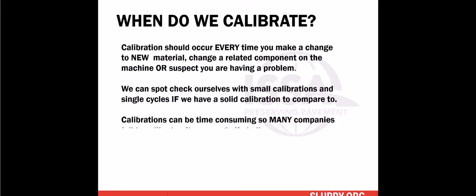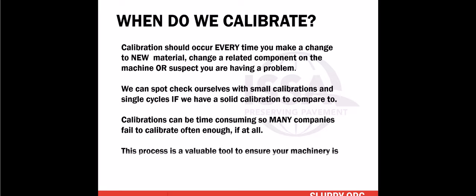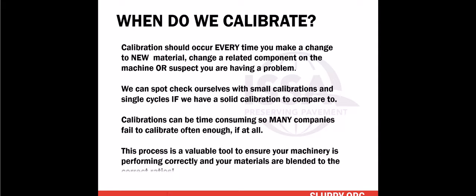So calibrations can be time consuming, so many companies fail to calibrate often, if at all. I have run into folks who just don't calibrate, they don't see a value in it, and it's fairly sad. It hurts you in the long run because when problems occur - and in the real world they do - it's going to happen. Calibrations allow you to know where you're at.